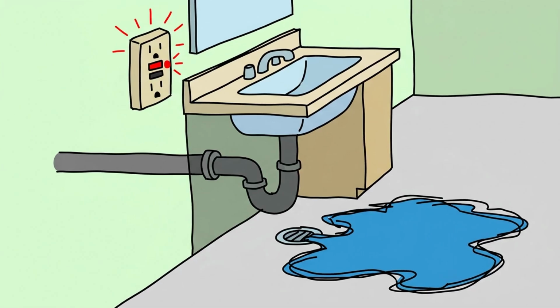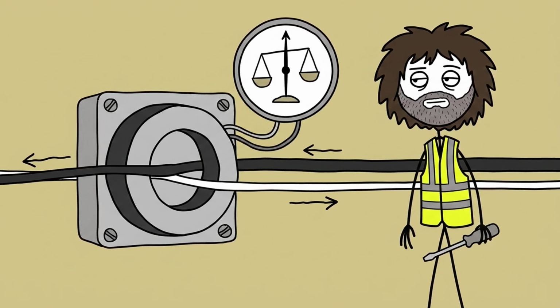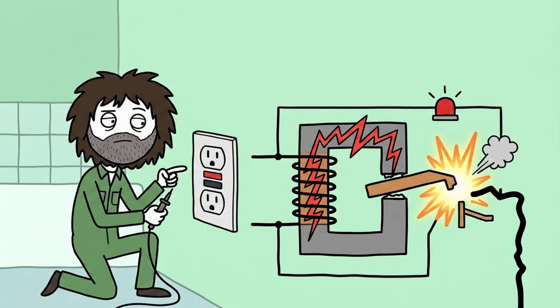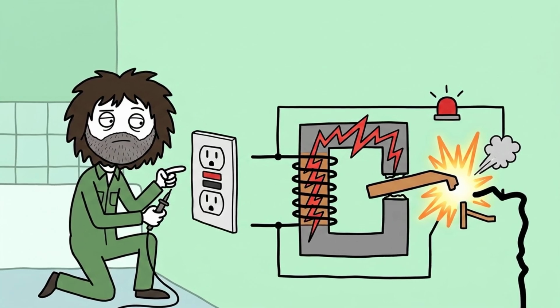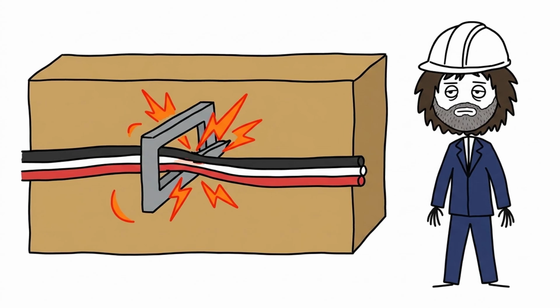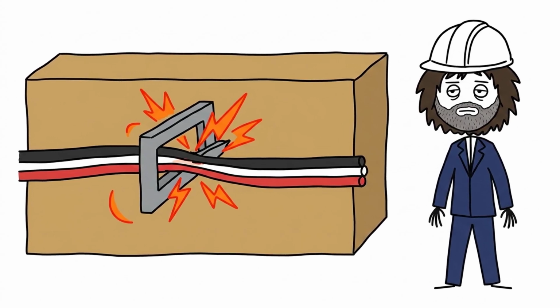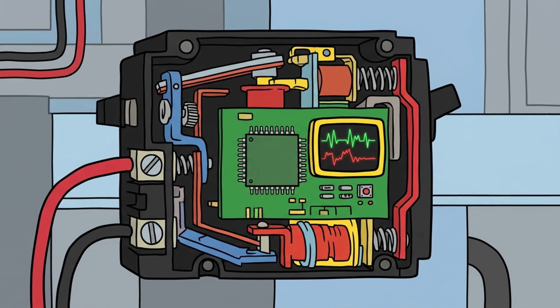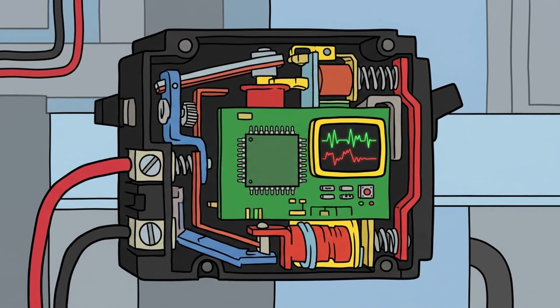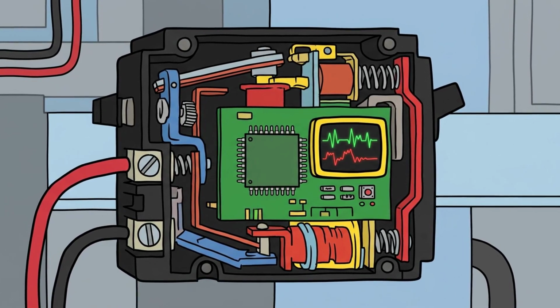As the arc forms, magnetic fields draw the plasma wave into the chute, splitting it into smaller, cooler arcs until voltage collapses and the circuit is quenched. Standard thermal magnetic breakers protect copper wires from overheating, but they are completely blind to two dangerous electrical hazards: low current electrocution and high resistance arcing.